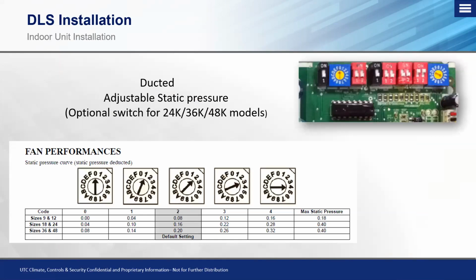So on our ducted style units, we do have adjustable switches on here that we can set for static pressure. Please be aware that the units do not come set with the maximum static pressure that they can output. So don't assume that you're automatically going to get the amount of static pressure you need to satisfy the spaces that this ducted unit is serving.